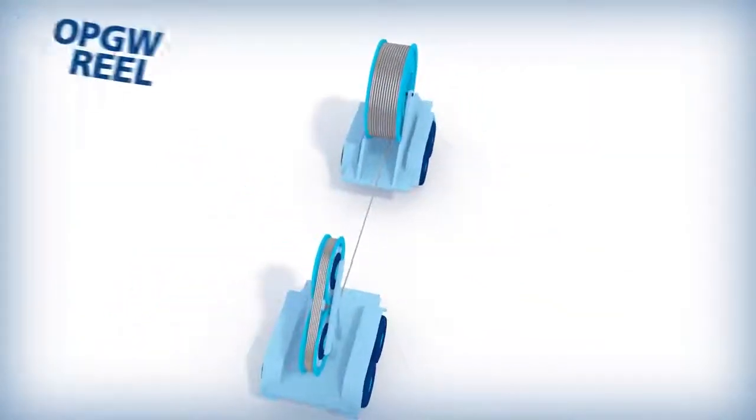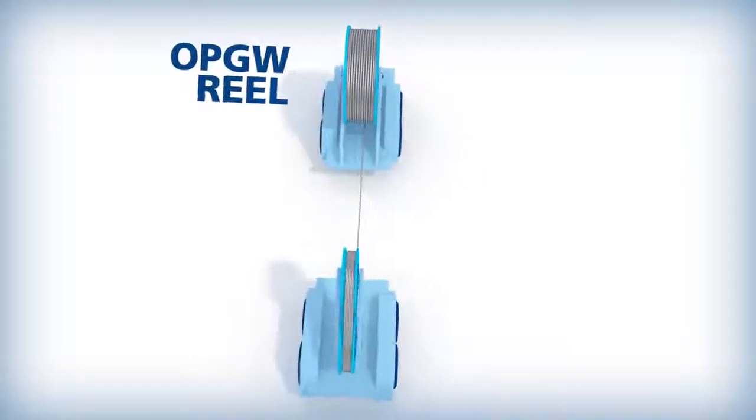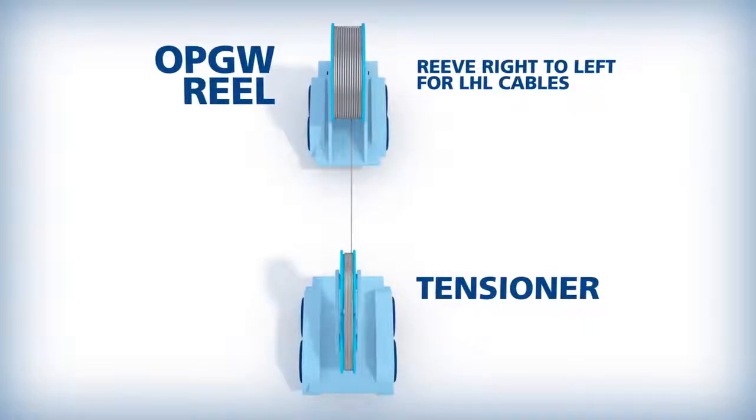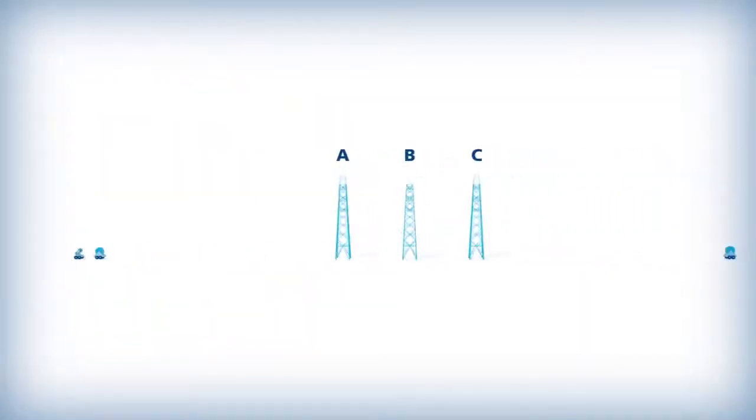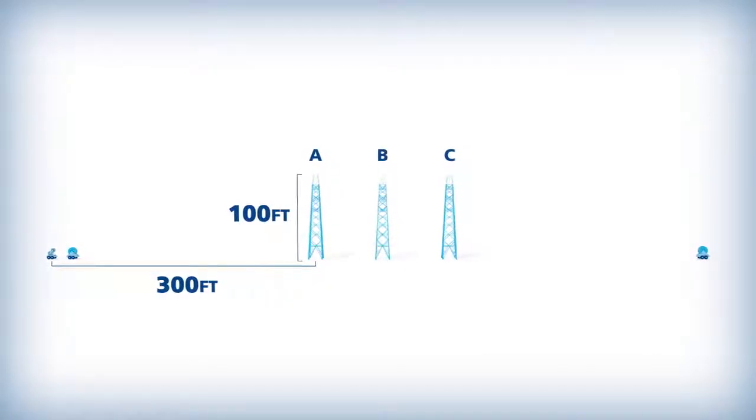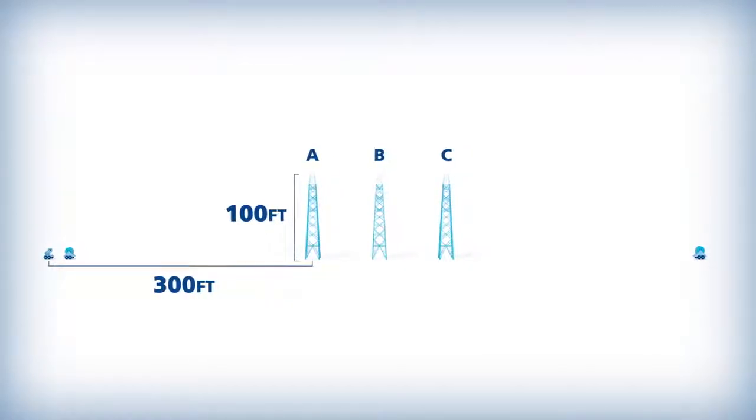The OPGW reel should be placed directly in line with the tensioner, and the OPGW should be reeved through the bullwheel properly. The tensioner should be located at a 3 to 1 ratio to the stringing block on the first structure and also be in line with the first two structures.